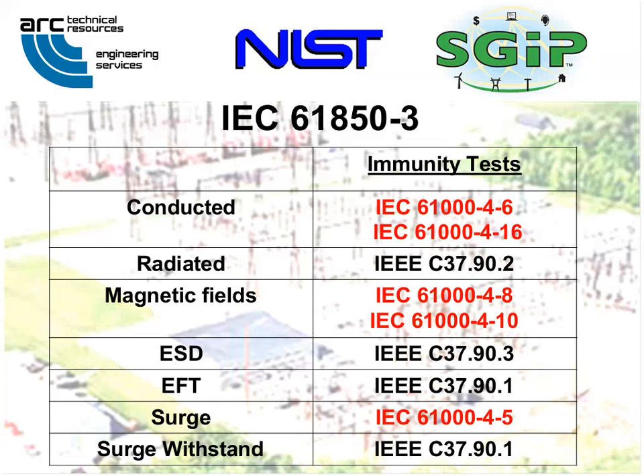A terribly obvious gap was surge, 61000-4-5. American standards didn't require utility products to resist lightning strikes. Indirect lightning strikes five miles away. Well, if the vendors hadn't been testing for this, their stuff would have already blown up. So the truth of the matter is we were just catching up to what the reality on the ground was. American manufacturers were testing for surge. They had to, or the products wouldn't survive.